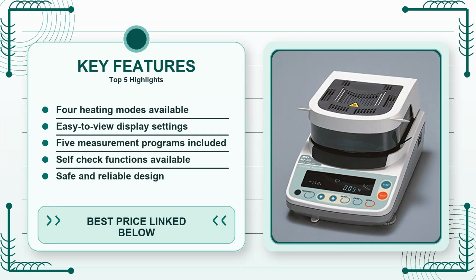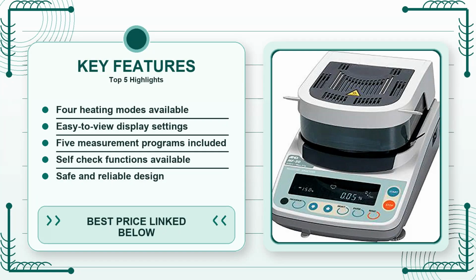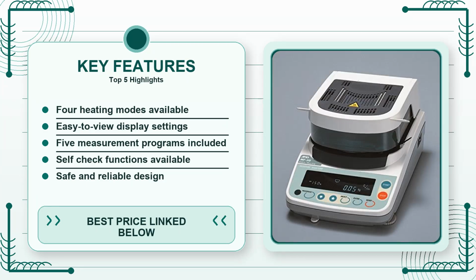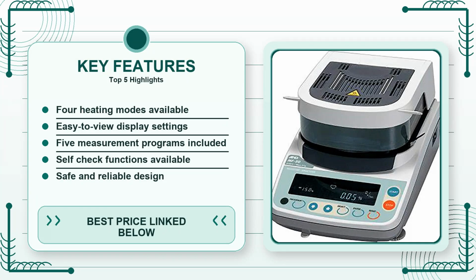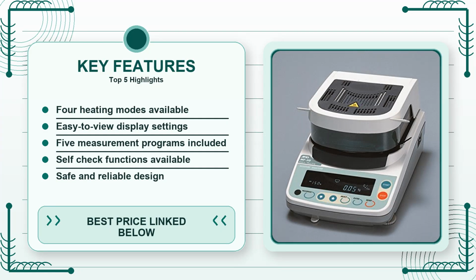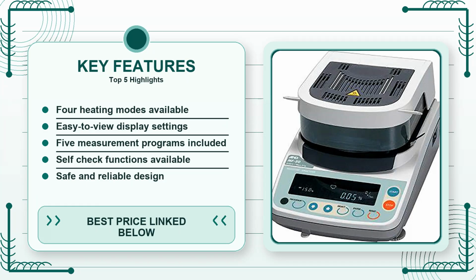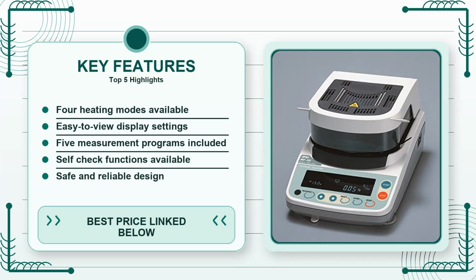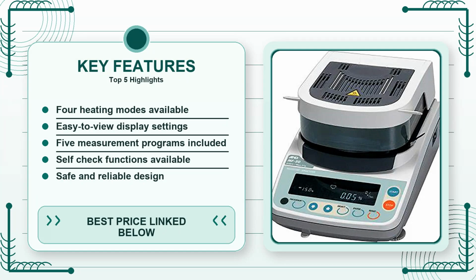Who should actually consider the MX50? If you run a small to medium lab where you need to run multiple samples a day and you can't afford a full-size thermogravimetric analyzer, this balance hits a sweet spot. It offers 5 selectable measurement programs, so you can store a routine for, say, a 30-minute drying at 105°C for food samples, and another for a slower 70°C run for delicate pharmaceuticals. The 4 heating modes give you granular control over ramp-up speed, which is a real time saver when you're dealing with a mix of quick-dry and slow-dry materials. The vacuum fluorescent display, VFD, is bright enough to read in a dim lab corner, and the progress window shows real-time weight change, so you can walk away for a coffee and come back knowing exactly where the process is.